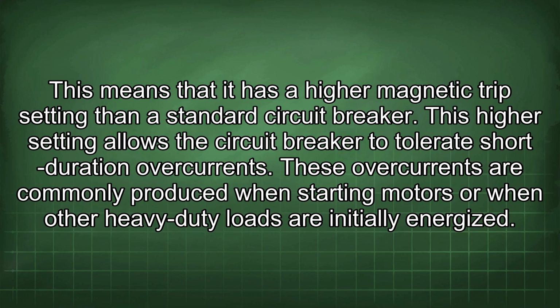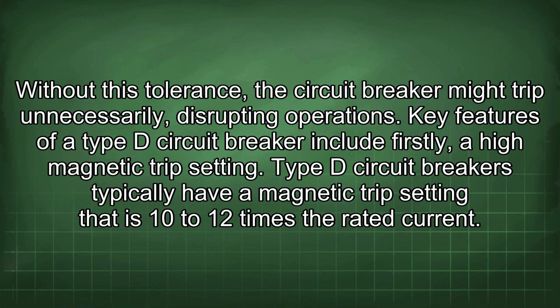This means that it has a higher magnetic trip setting than a standard circuit breaker. This higher setting allows the circuit breaker to tolerate short duration overcurrents. These overcurrents are commonly produced when starting motors or when other heavy-duty loads are initially energized. Without this tolerance, the circuit breaker might trip unnecessarily, disrupting operations.